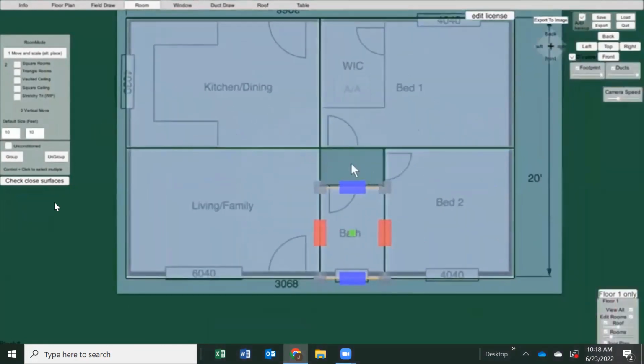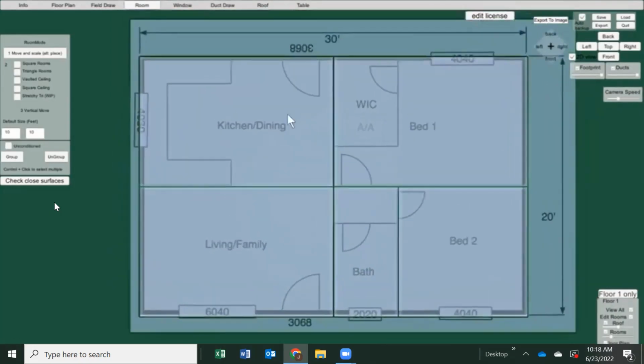Now you notice we can put a block here for this hallway, but since it's not gonna get a register, it's gonna get a return grill, but it won't get a supply register. We'll just include the loads for that in the bath, and all we do is just make the bathroom bigger. Now you know this house is 30 by 20, so it's gonna be 600 square feet. So according to the plans, this house is 600 square feet.